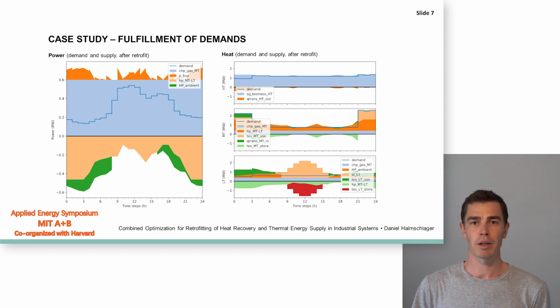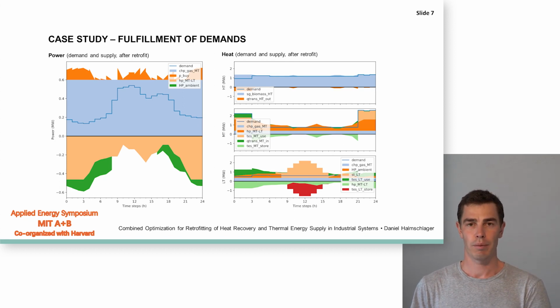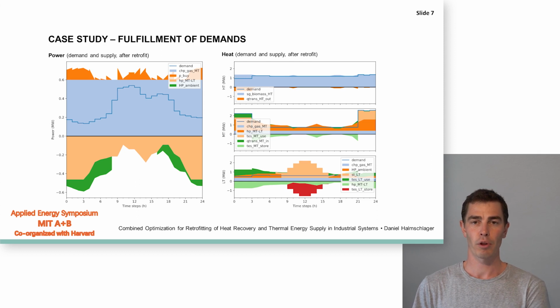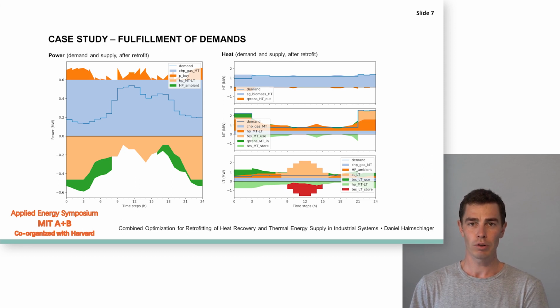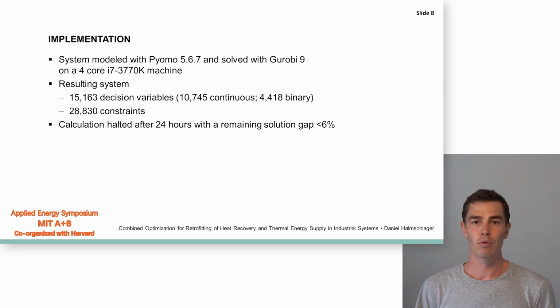Most of the medium temperature heat is supplied by the high temperature heat pump while utilizing the medium temperature storage. For the low temperature demand, shown at the bottom of the right chart, we can see that the heat provided by the solar thermal modules, especially around noontime, is distributed through the full 24 hours by usage of the low temperature thermal storage. Now a few words about the implementation.